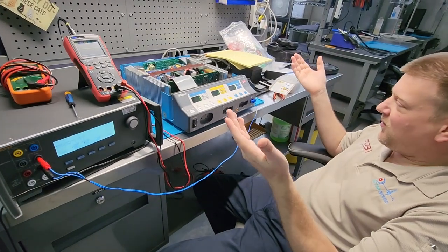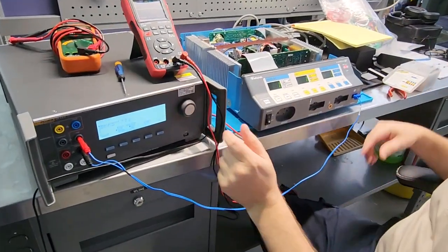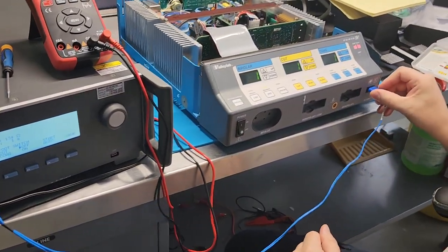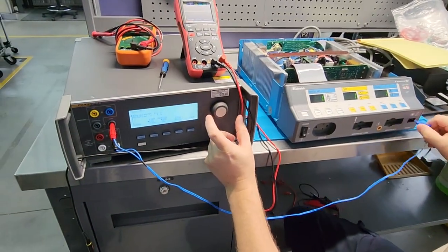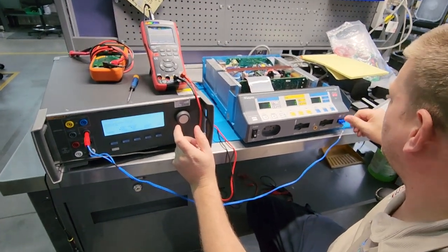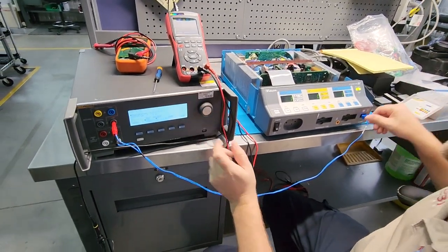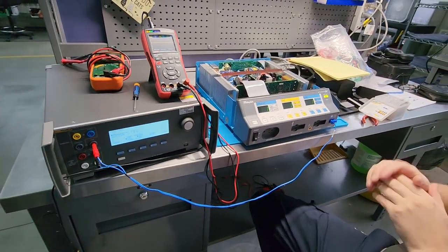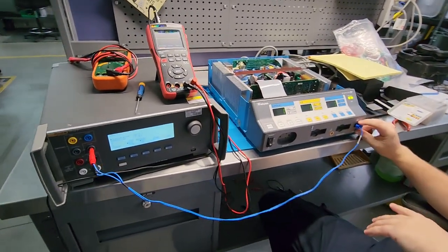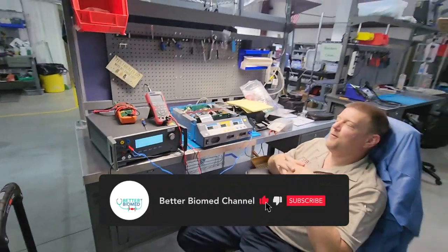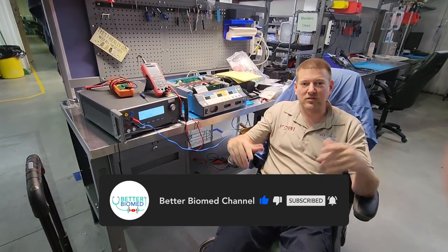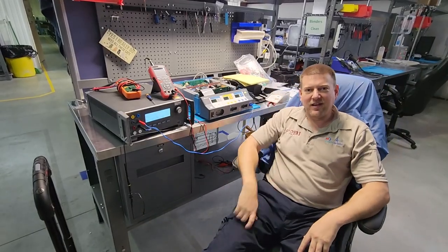There we go. Look at that. I plug it back in. It's showing that that is not good. Let's turn it down to 134. Unplug. Put it back in. Oh yeah, she's upset. There we go. Okay. So take it down below the tolerance level and we connect it back up and we are good to go. REM, this is the most important calibration on any ESU because that's the one thing that prevents a patient from getting burned. All right guys, thanks for watching.